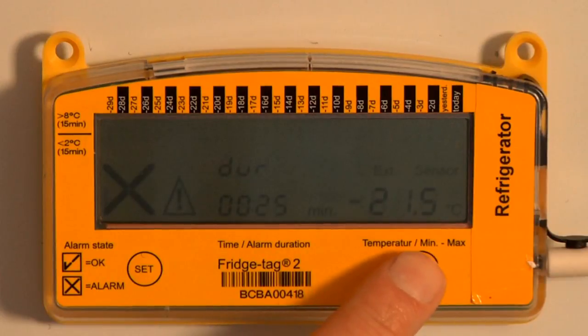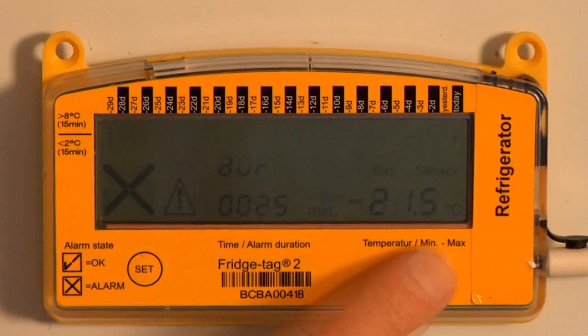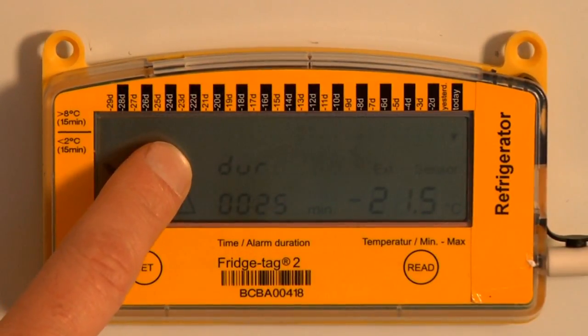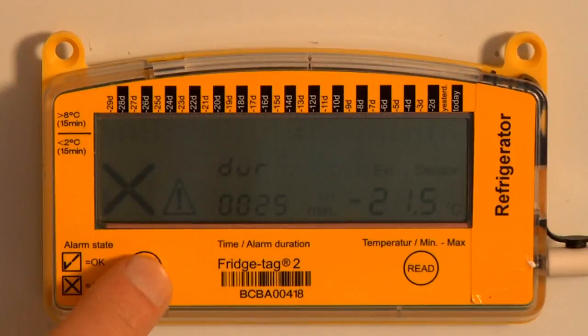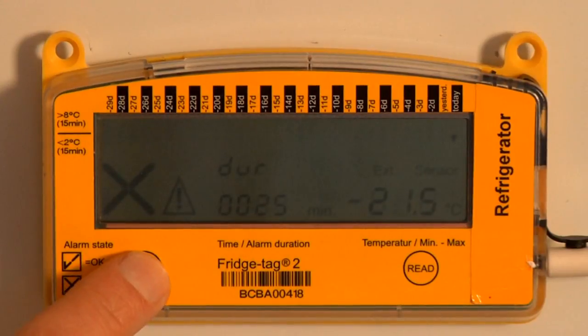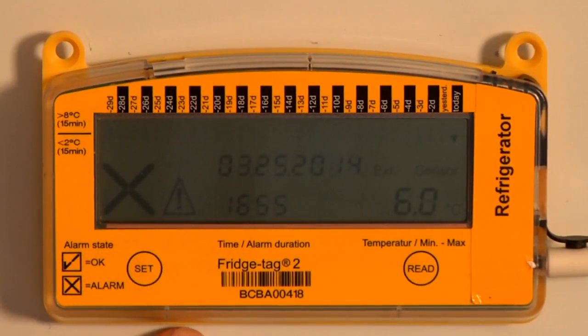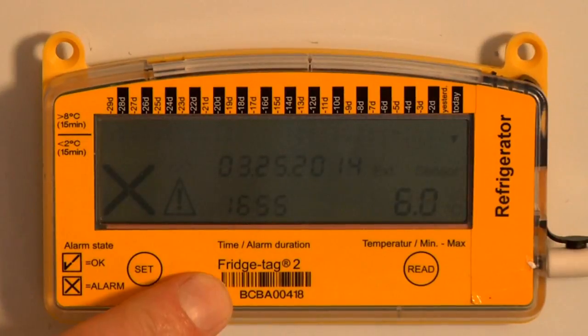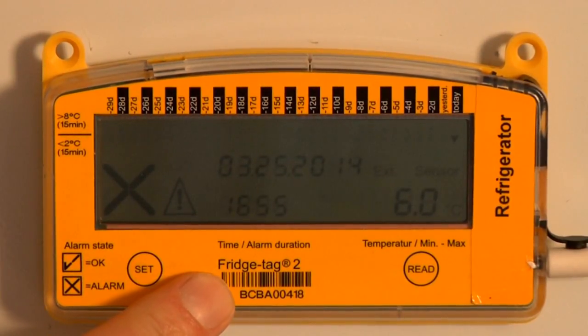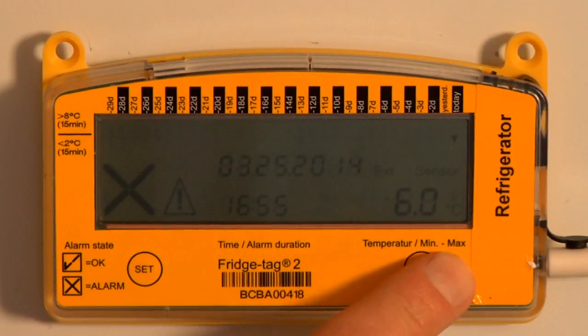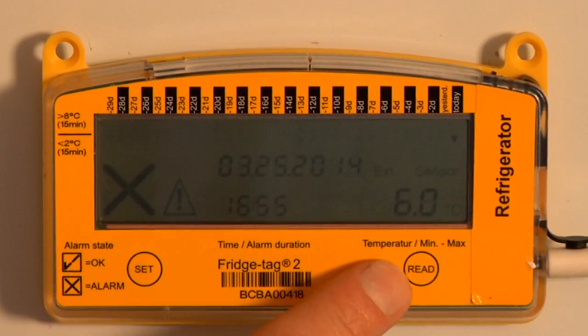If we press read, we can continue to read the history backwards, or we can press set again to come back to current status mode. The software in the Fridge Tag 2 is tracking when the read button is pressed.